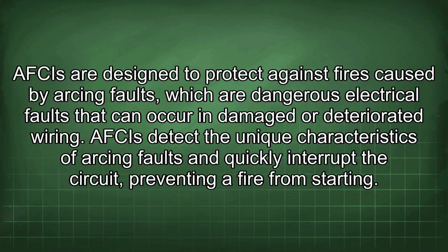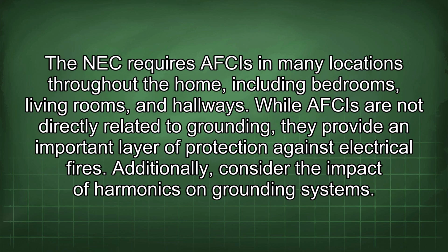Moreover, consider the role of arc fault circuit interrupters, or AFCIs, in electrical safety. AFCIs are designed to protect against fires caused by arcing faults, which are dangerous electrical faults that can occur in damaged or deteriorated wiring. AFCIs detect the unique characteristics of arcing faults and quickly interrupt the circuit, preventing a fire from starting. The NEC requires AFCIs in many locations throughout the home, including bedrooms, living rooms, and hallways. While AFCIs are not directly related to grounding, they provide an important layer of protection against electrical fires.